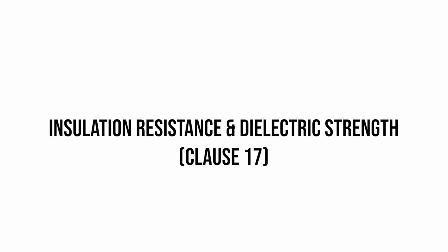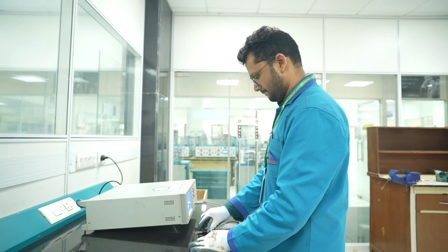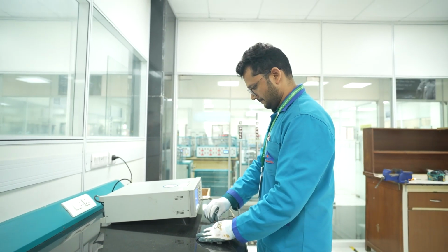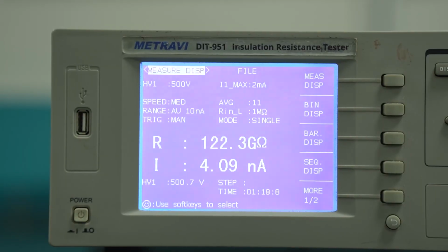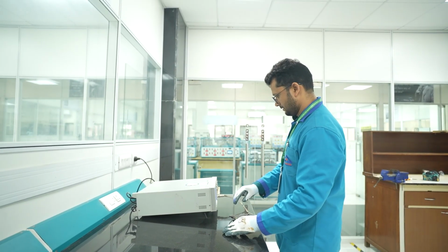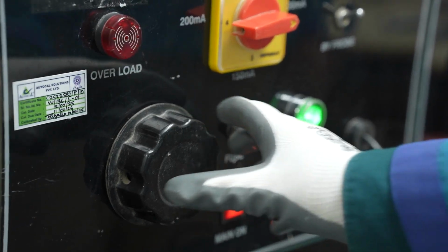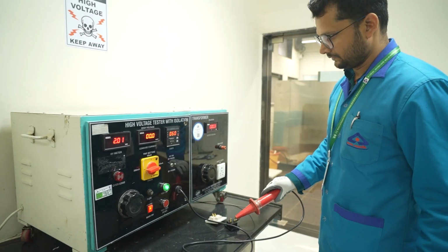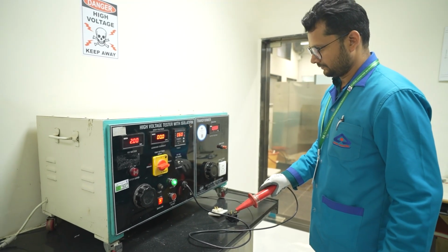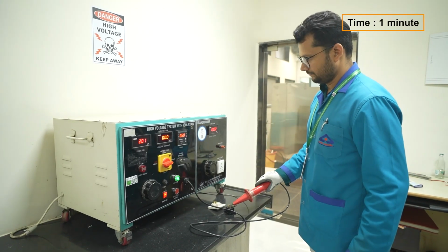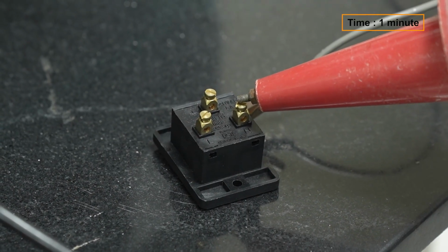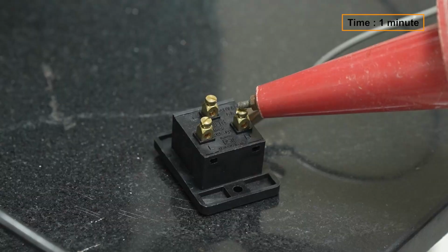Insulation resistance and dielectric strength. Clause 17. The insulation resistance is tested using 500 volt DC to detect any leakage. Additionally, a high voltage test of 2000 volt is applied for 1 minute to confirm the absence of electrical breakdown, ensuring safety and reliability.